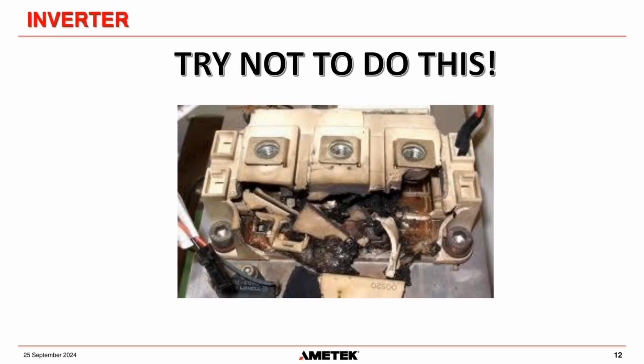The unfortunate thing about an IGBT is, unlike an SCR, which is very robust and can withstand high current situations for a relatively small to medium portion of time, IGBTs really cannot handle excessive currents. If something goes wrong, if the firing signal goes wrong, or you have shoot through, then a fuse really isn't fast enough to protect an IGBT, and this can happen. So we do have some circuits in place to try and prevent that from happening. But just remember, IGBTs are very, very sensitive devices to high current situations.